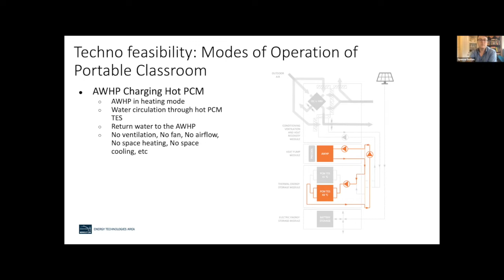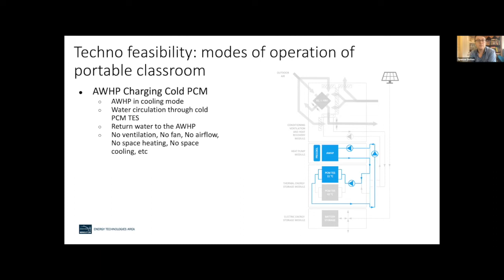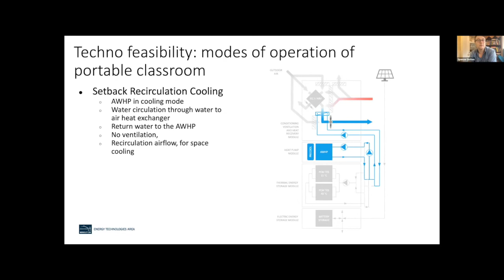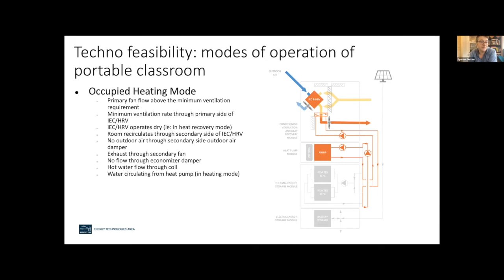Ultimately, it would look something more like this, as a package system where, for example, you can use the heat pump during off-peak periods to charge, during the winter mode of operation, to store heat energy. You could also alternatively use the heat pump to store cold thermal energy. Then you can imagine a scenario where you leverage just the heat pump itself to provide space conditioning, or alternatively provide cooling to the space, for example, or use these in conjunction with ventilation heat recovery.